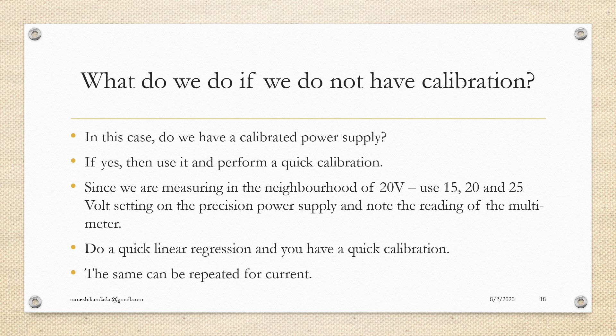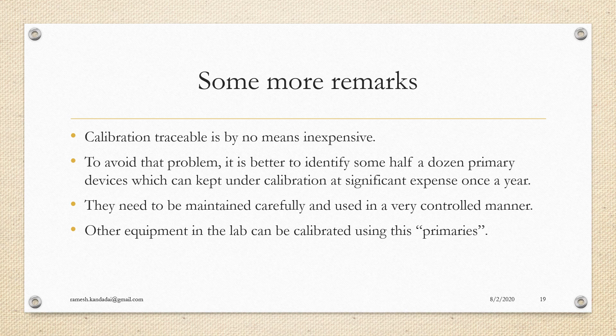Calibration and traceability is not cheap. And that is why I recommend identifying logically certain apparatuses in the lab and keeping them in calibration. For instance, if you keep a precision power supply, you can calibrate all the multimeters, oscilloscopes, everything. Similarly, if you keep one box of primary weights, you can calibrate all your balances. Like that, it's easy to identify 3 or 4 primary devices and keep them in calibration so that the rest of the equipment in the laboratory can be calibrated using these primaries.